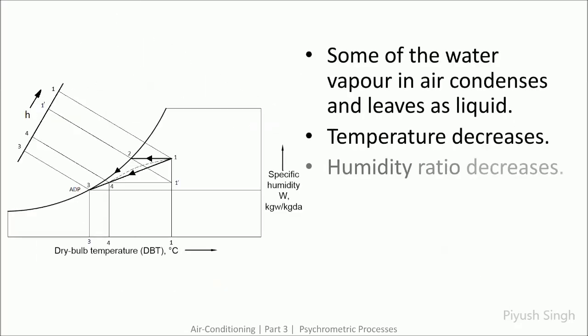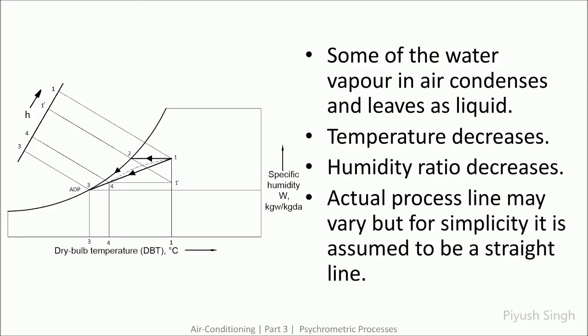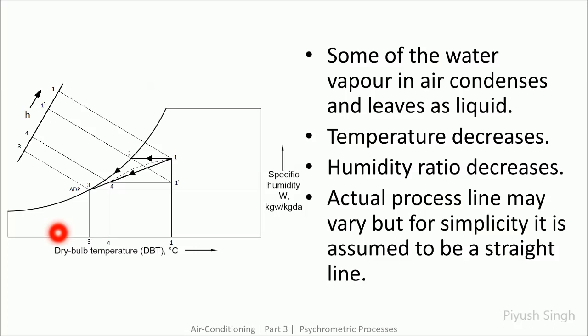In this process, some condensation takes place, so there is a net drop in moisture content of the incoming air and hence a drop in specific humidity. There is also a drop in dry bulb temperature. Since we are approaching the saturation line, relative humidity increases. There is also a drop in specific enthalpy.